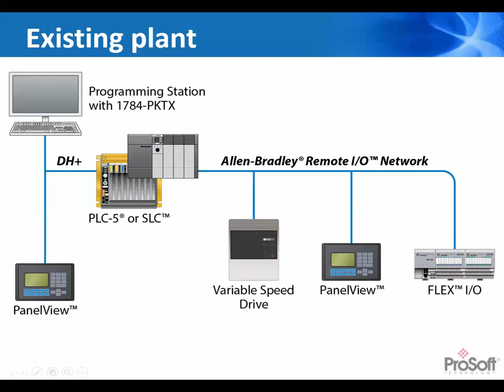So let's look at an example of an existing plant and see where we can look at a phased migration. So we've done our installed base evaluation, and we've identified a few critical areas of the plant, whether it's the aging PLC system or the aging DH Plus network, or the drives, the panel views, or even the I/O. And we can look at each of these aspects individually. So with a phased migration approach, we can look at the drives, for example. You may have some older 1336 drives on your plant that you need to migrate up to the latest PowerFlex, which can then begin to introduce an Ethernet IP network through our gateway without making any changes to the ladder or code of the existing PLC ranges. So you're not changing anything on the plant, you're simply adding some new equipment.